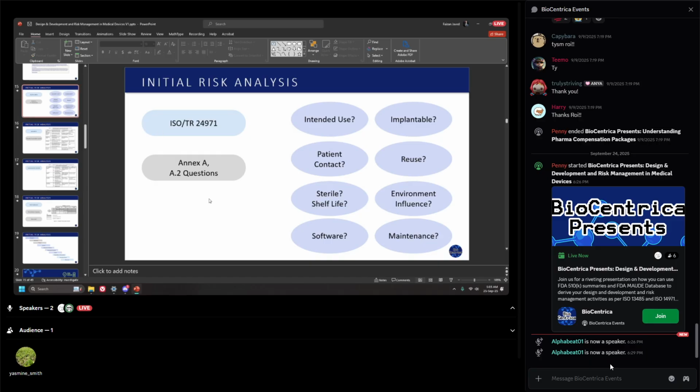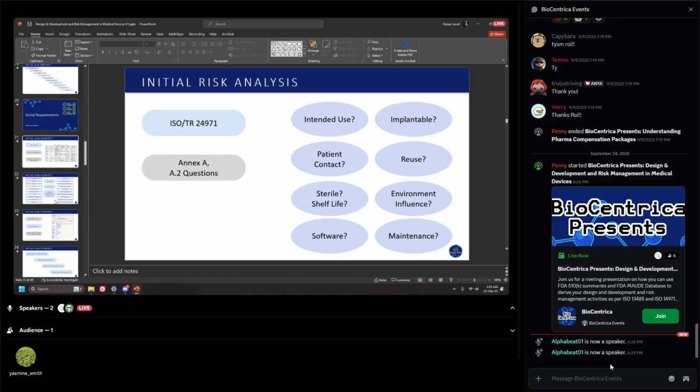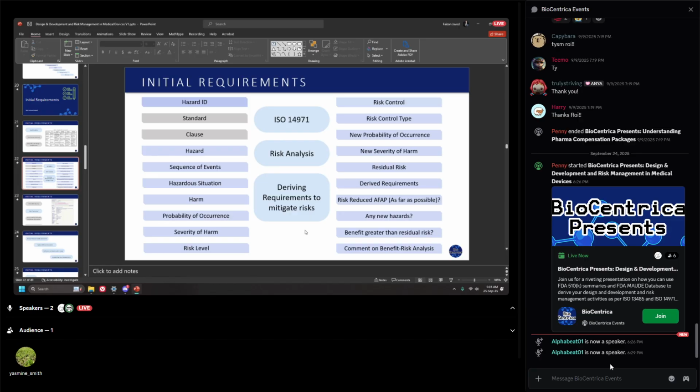Yeah, and before that, you create a risk analysis plan. And in the end, when you perform all of this for all of your processes, your design, your manufacturing process, and your use-related risk analysis, you do a risk analysis summary report, and that's basically your complete set of files we'll call risk management file.